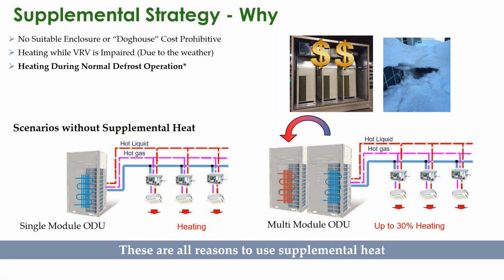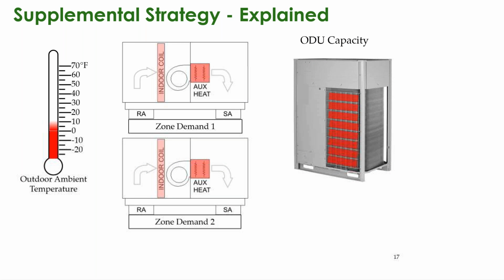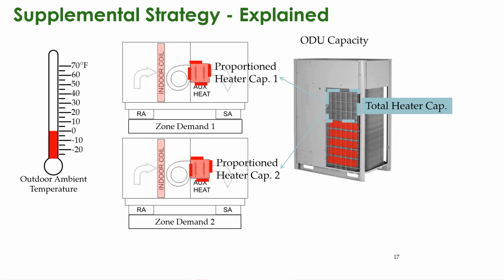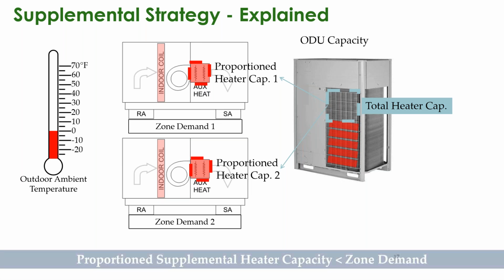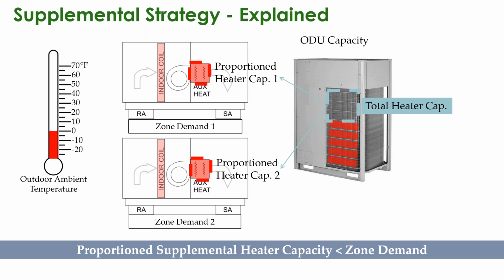in these times where you're either no heating or low heating, especially on days where you have a high loss because the temperature has gotten very cold. So as the temperature is dropping outside, the outdoor capacity is reducing. This is when you would bring on proportioned supplemental heat at the individual zones. The proportion of that total loss of that outdoor unit, you would proportion across those zones based off of their size. The proportion supplemental heater capacity should be less than the total zone demand because we're expecting that we're going to be getting some capacity out of the variable refrigerant system at that time.